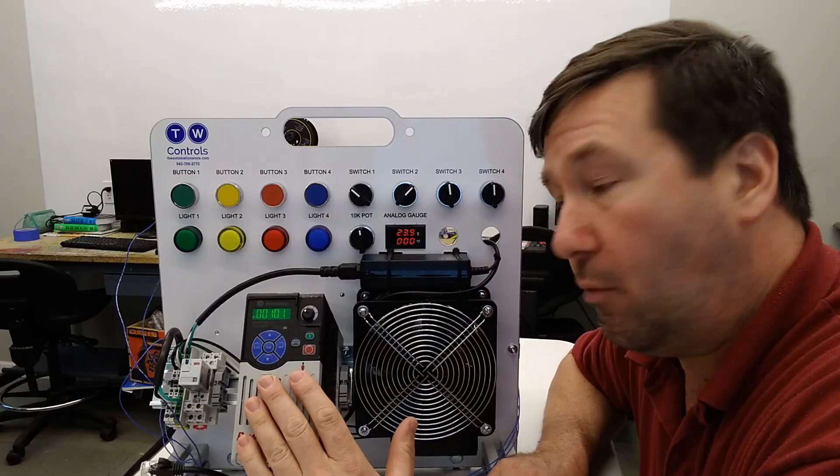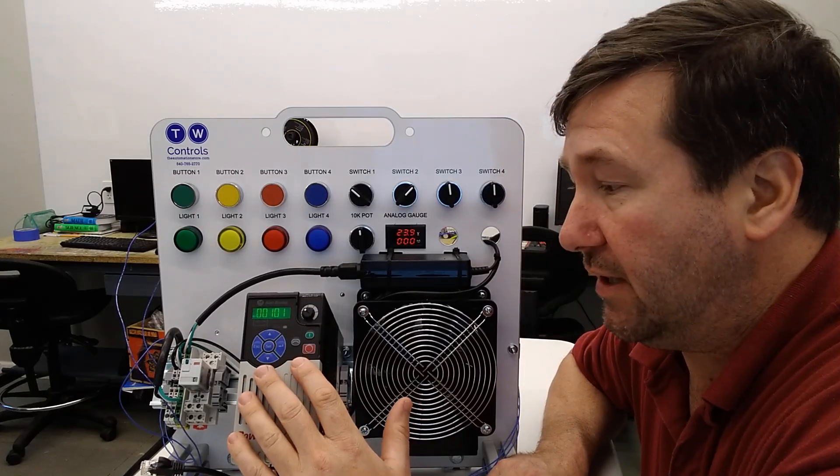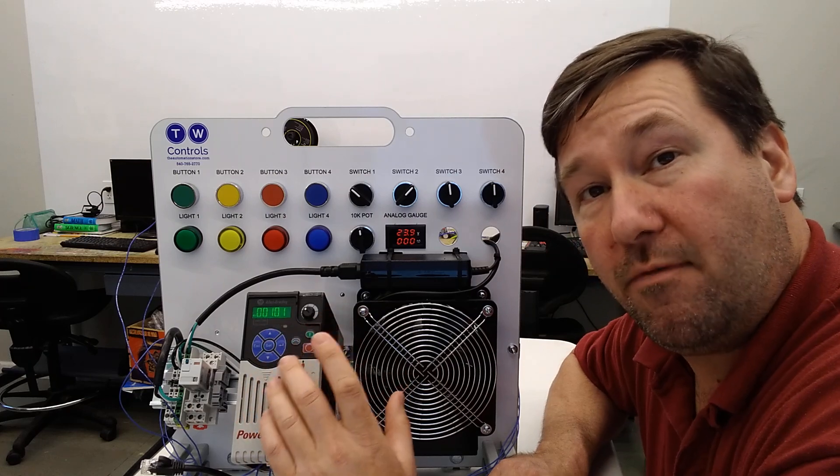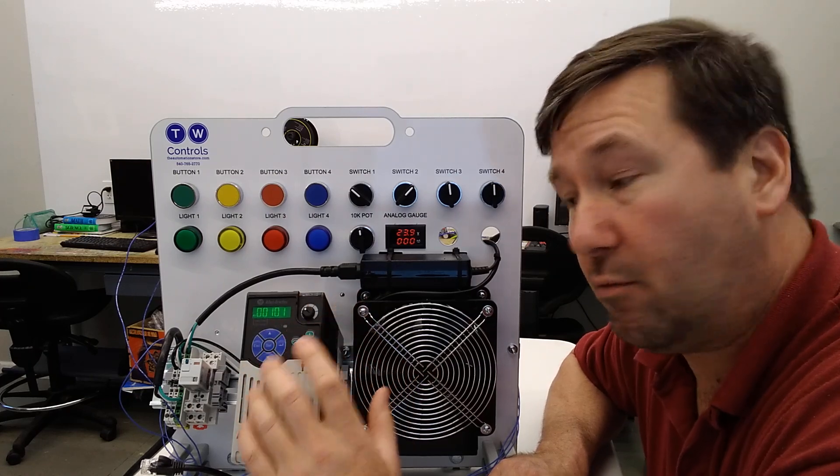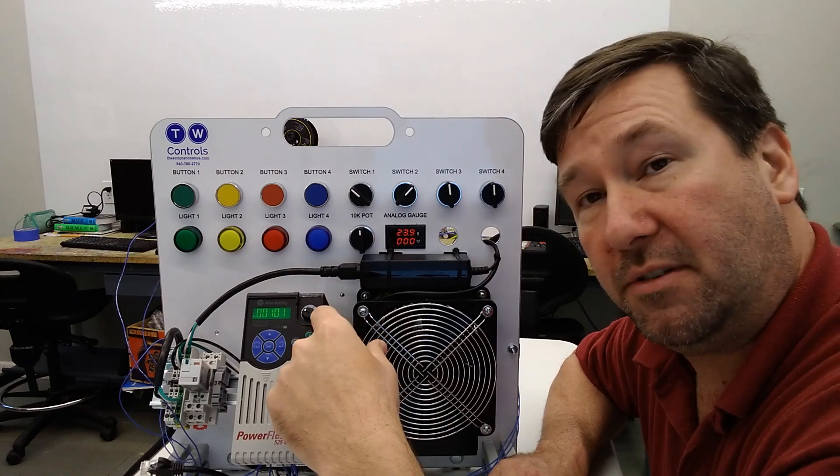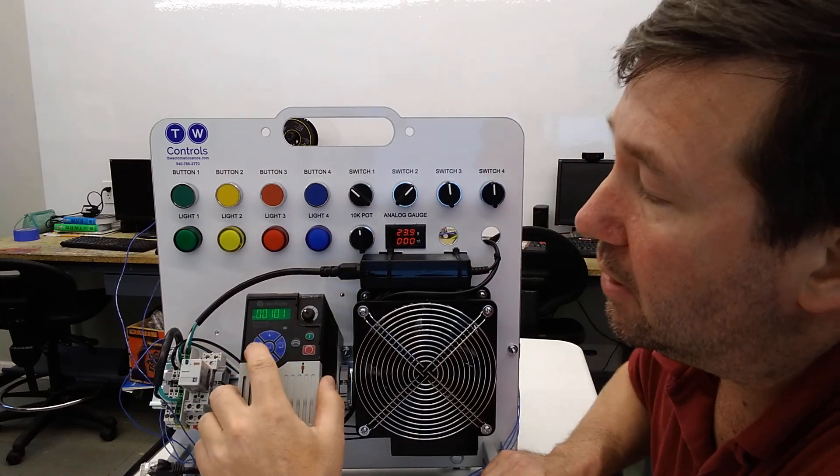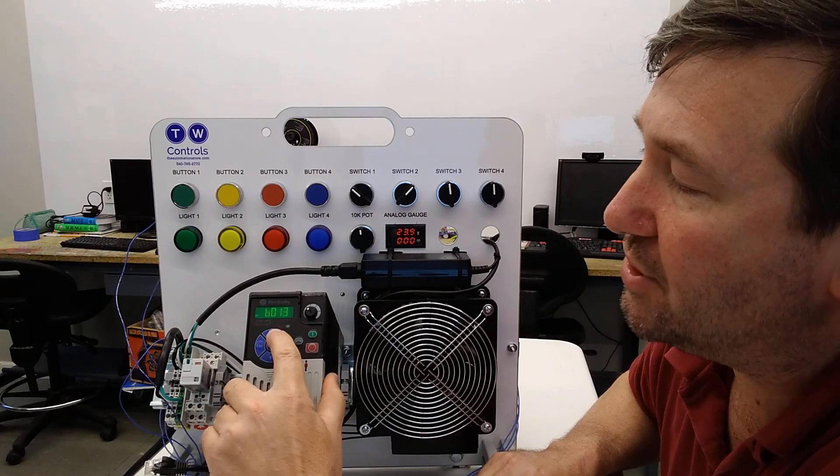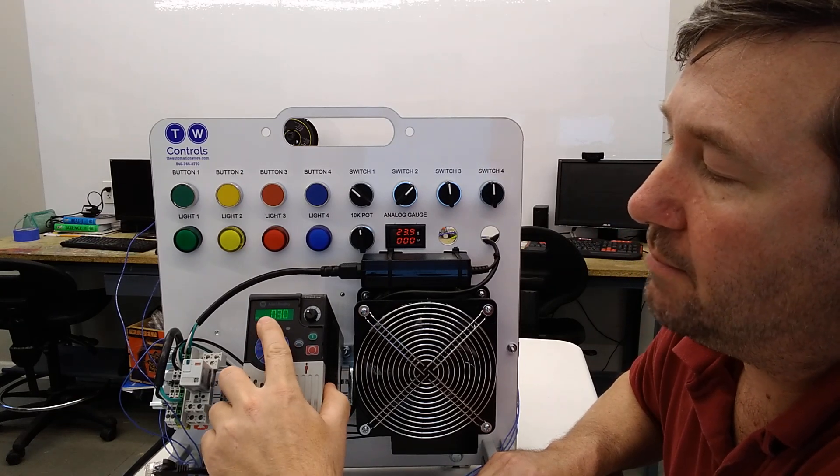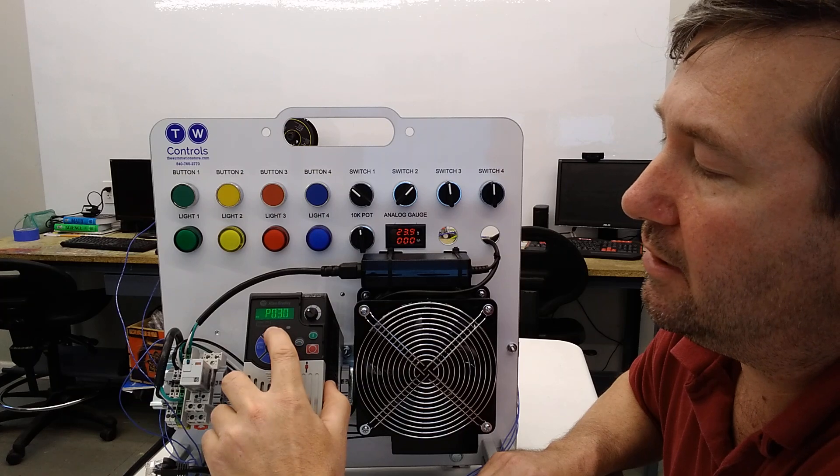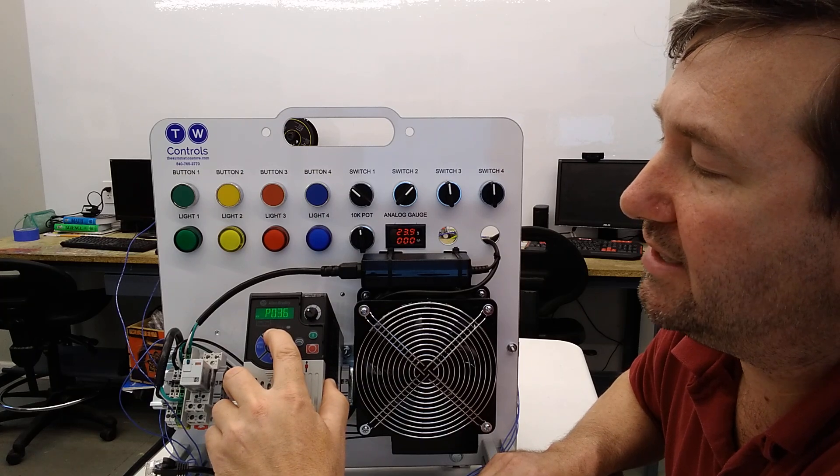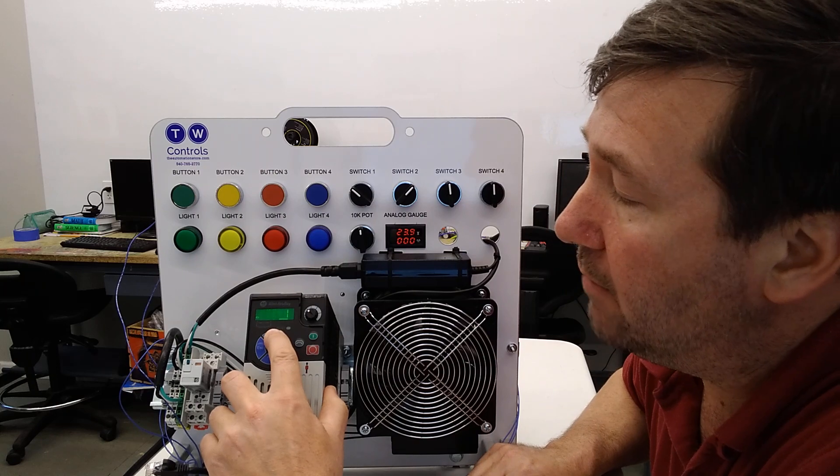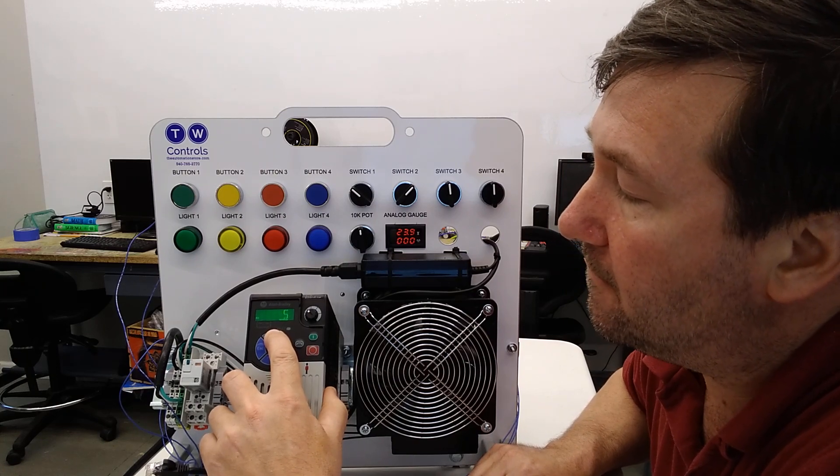So we do need to change one parameter in our PowerFlex drive, and that's going to be parameter P047. And that is our speed reference. And by default, it's up here on this built-in potentiometer. So we're going to hit the escape key until we see the B flashing. And we'll press the up key to get to P. And we'll hit enter. And then we're going to go up to 47. And it defaults to one. And we want to put that up on five.